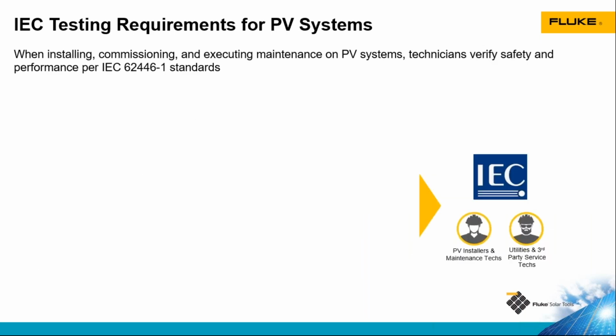Now, talking about the IEC 62446-1 standard, this is the standard for documenting and testing grid-connected photovoltaic systems. It's a requirement in many European countries when you build or troubleshoot or modify a PV system, you need to do testing to this standard, document it, and provide that documentation to the system owner.